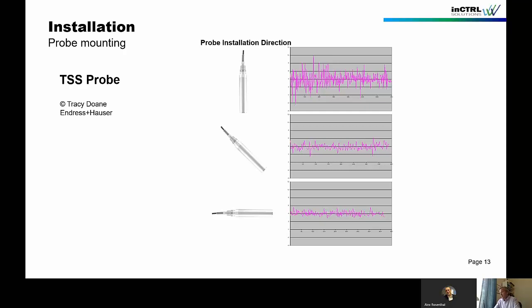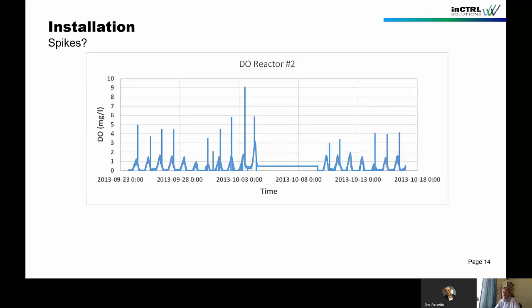What that means is that if the installation is wrong, you're actually measuring air bubbles. For that TSS probe, an optical probe, the air bubbles are actually an interference, so they disturb the measurement process. A nice highlight of installation and the impact it can have.